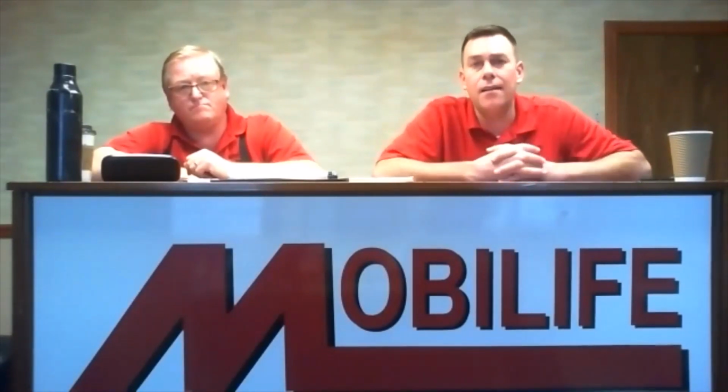Do I need one? Yeah, so it sounds like somebody has taken the anode rod out and put in some sort of a petcock drain valve or something. The water heater really does need an anode rod in it. It stops the effects of electrolysis. Instead of eating away at the tank liner itself, it eats away at the anode rod instead, and prolongs the life of the water heater tank. So yes, I would recommend that other valve system come out and an anode go in.